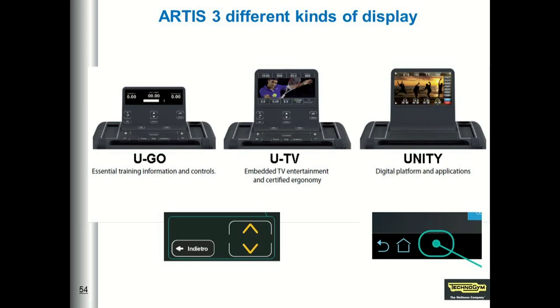For Artis UGO and UTV, to enter the configuration menu and perform the same steps seen for VisioSelf and VisioWeb, you must press the up and down buttons and at the same time press the back button on the console. For Unity, you must press an area of the touch screen next to the home icon. Once you have done this, the device will show the login page where you can insert the password — the same passwords used for VisioSelf and VisioWeb: 2501 for the service menu and 2406 for the user menu — and you can do the configuration in a very similar way to the other two hardware devices.